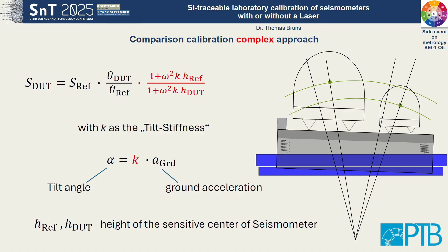Then you can apply a correction, and actually you can apply two corrections. I don't want to go into the details there. If you make these corrections, then you get the red or the green curve that I display here. The blue one is the original primary calibration that was not yet corrected. So this is the wrong primary measurement for the high frequencies. Here only the high frequency part from 1 Hertz is displayed.